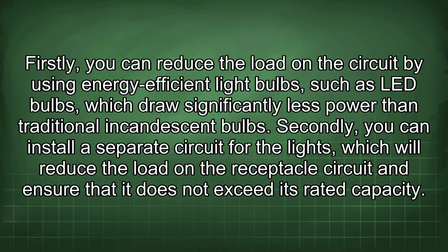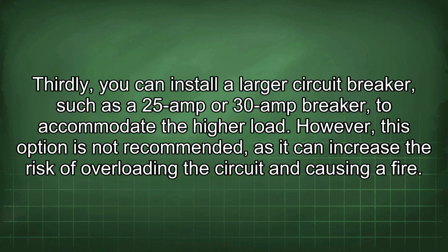Secondly, you can install a separate circuit for the lights, which will reduce the load on the receptacle circuit and ensure that it does not exceed its rated capacity. Thirdly, you can install a larger circuit breaker, such as a 25 amp or 30 amp breaker, to accommodate the higher load. However, this option is not recommended, as it can increase the risk of overloading the circuit and causing a fire.